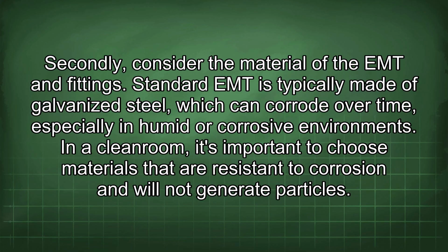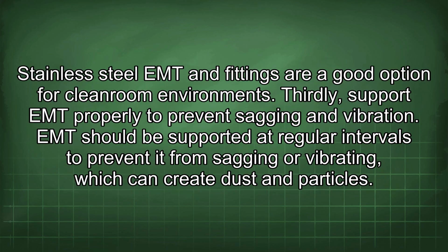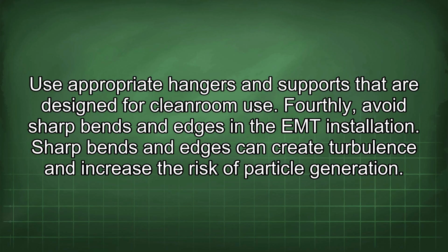In a cleanroom, it's important to choose materials that are resistant to corrosion and will not generate particles. Stainless steel EMT and fittings are a good option for cleanroom environments. Thirdly, support EMT properly to prevent sagging and vibration. EMT should be supported at regular intervals to prevent it from sagging or vibrating, which can create dust and particles. Use appropriate hangers and supports that are designed for cleanroom use.